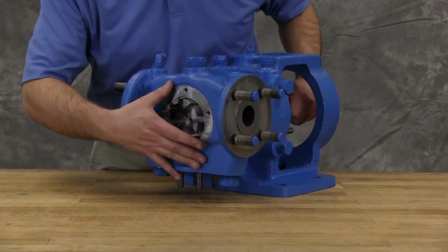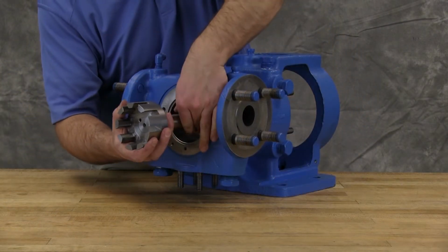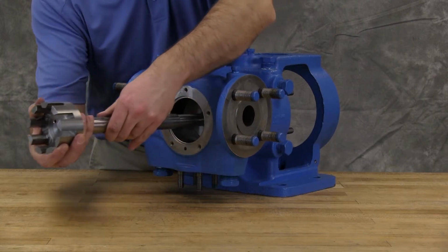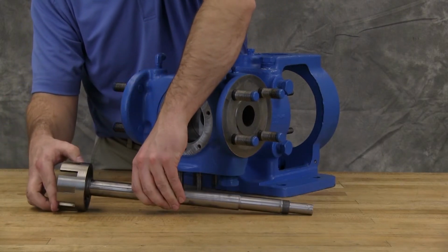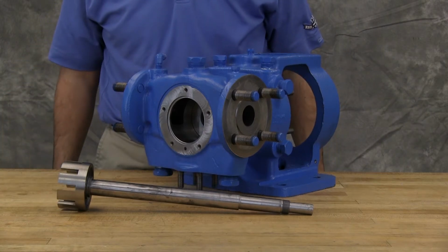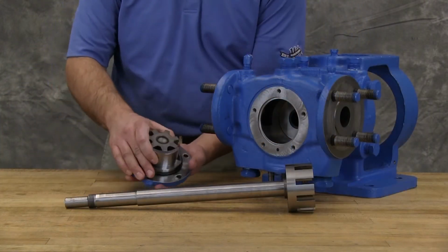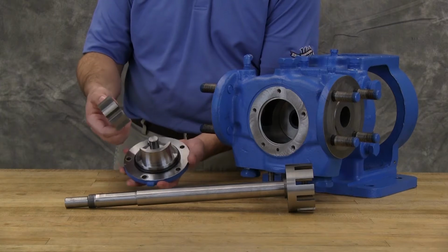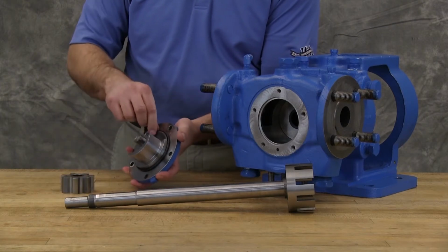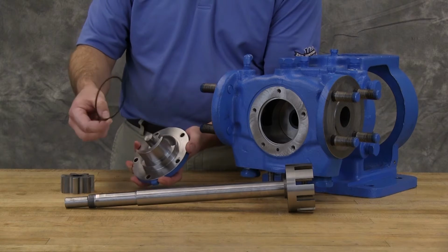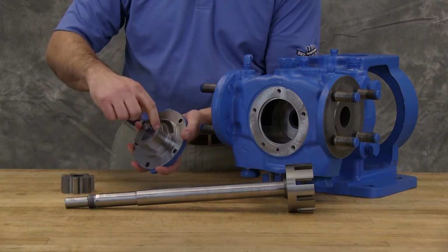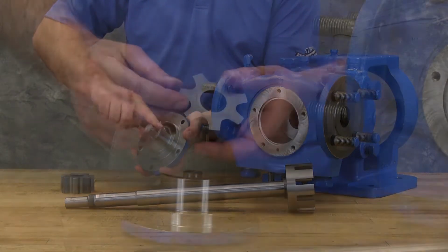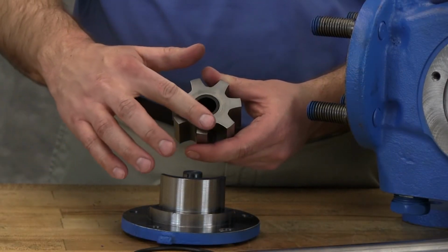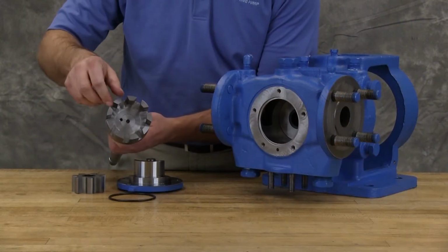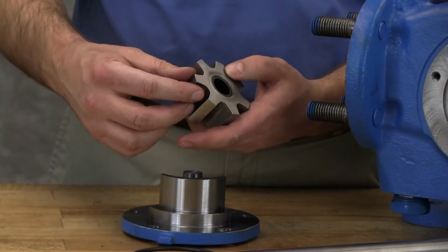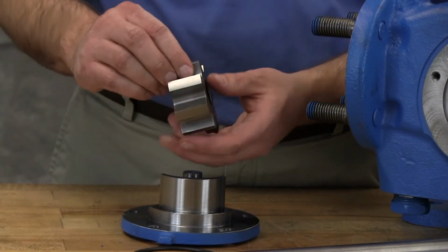The rotor and shaft assembly can now be removed from the pump. A soft-headed hammer may be required to tap on the end of the shaft for removal. Take care in removing the rotor and shaft to avoid damaging the bracket bushing. Remove the idler from pin. Remove O-ring from head. Inspect pump parts for wear, particularly critical parts such as the idler pin, idler bushing, bracket bushing, idler gear, rotor, shaft, and casing. Check parts for nicks, burrs, and excessive wear.